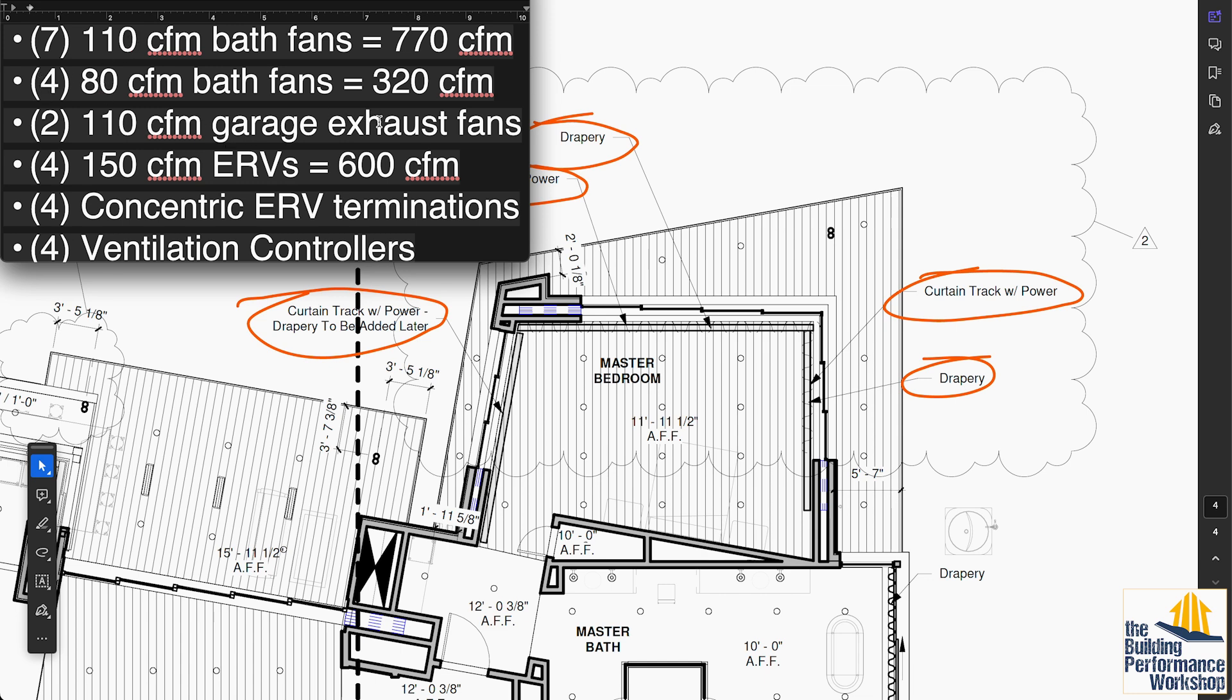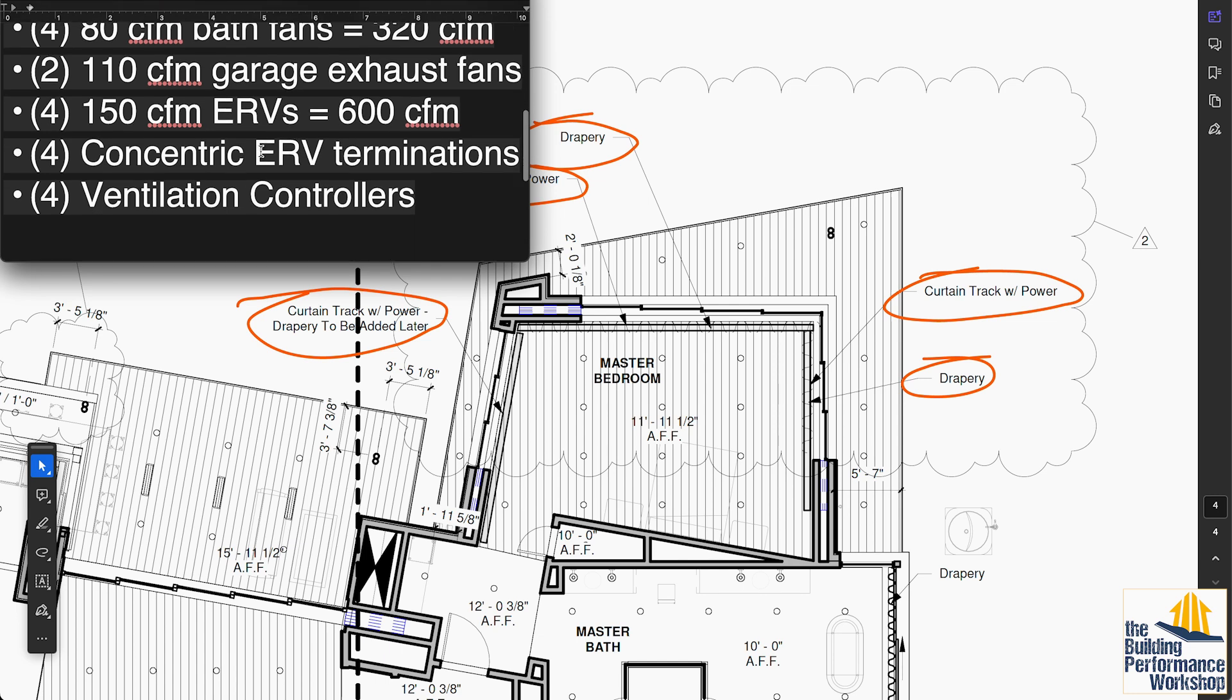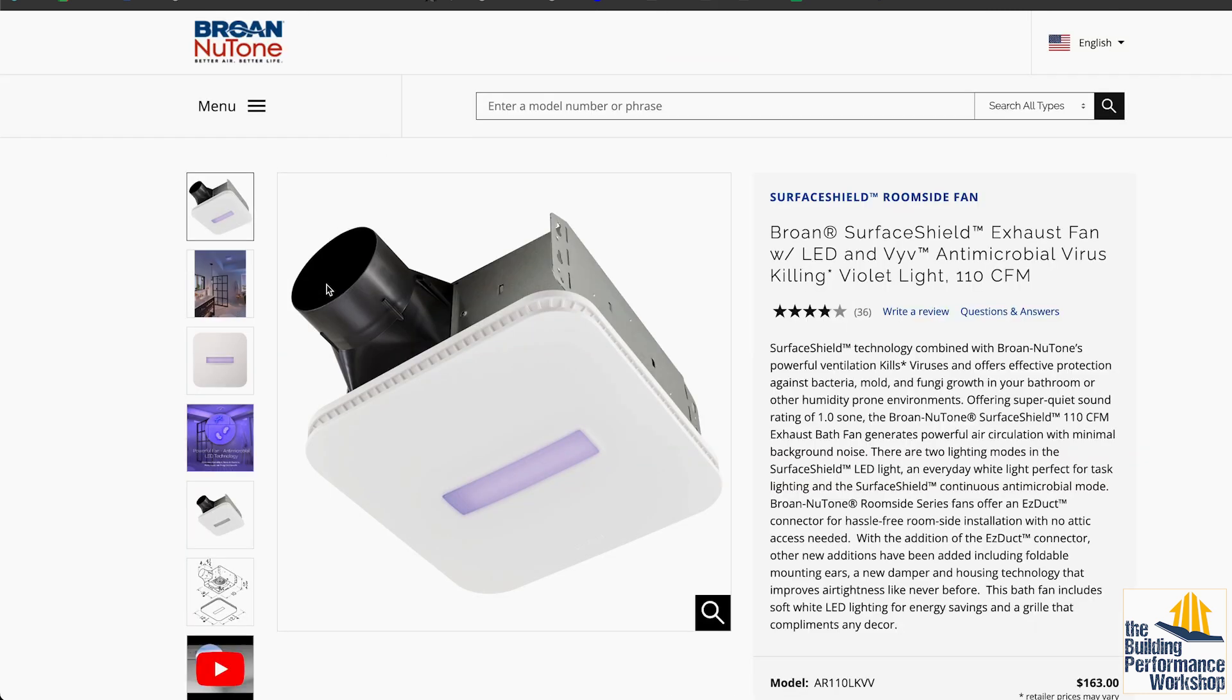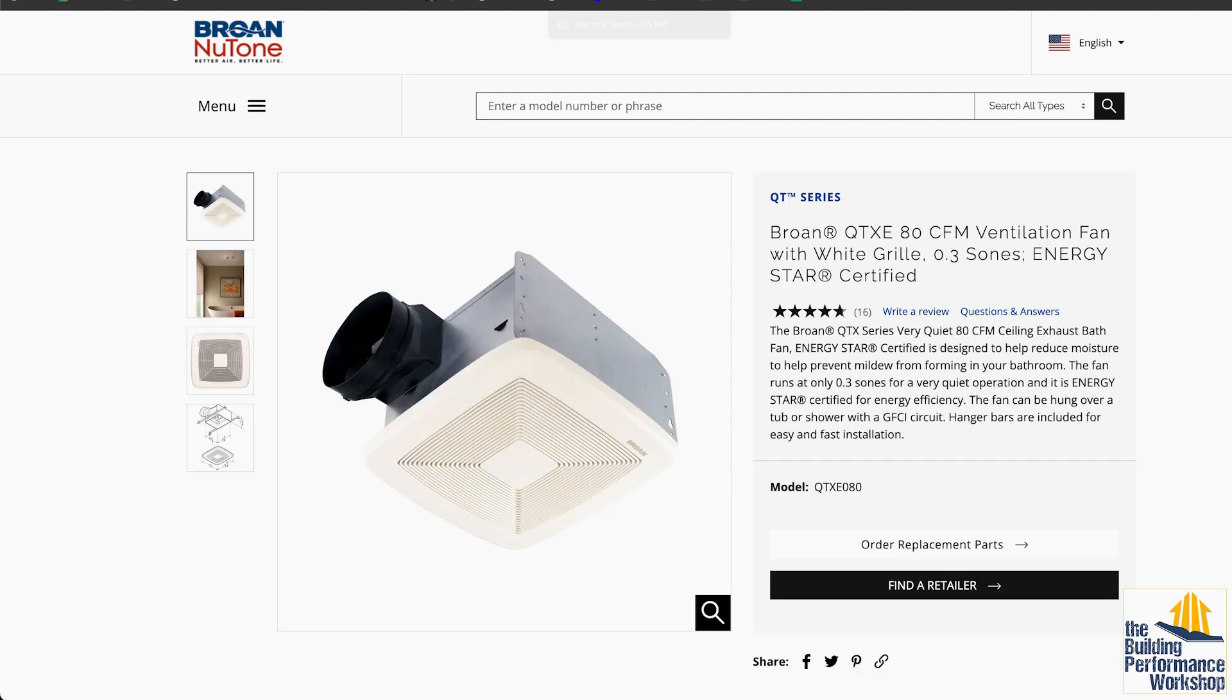Let's look at what they have installed in here. All those bath fans weren't extract points for the ERV. They're actual honest-to-God bath fans. They have 7 110-CFM bath fans, they have 4 80-CFM bath fans, they've got 2 in the garage which we're not counting for this. What I'm worried about right now is depressurization of the house. Exhausting out of the garage is fine. That's good. That's the only way to make sure that the garage is depressurized with relationship to the house so you don't have infiltration the other way. We also have 4 150-CFM ERVs. That's 600 CFM. Now I'm going to assume that one of these 110-CFM bath fans and one of these 150-CFM ERVs is for the casita, so we're going to subtract that when we talk about this in a minute.